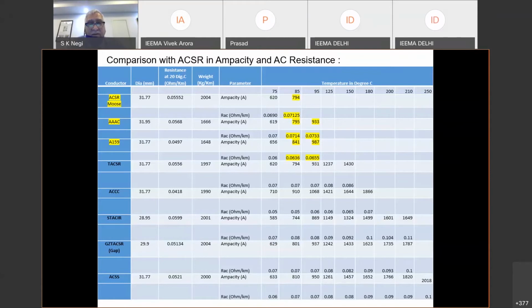Now, one more thing I want to convey here is my experience. When we do this transmission system development, I find that there are a lot of variations in the loading of the transmission line over a period of time. At one time, the transmission line will be heavily loaded; particularly not interstate lines, but within the state, when development takes place, I find that the line which was heavily loaded has now become moderately loaded, and then other lines come into the picture.